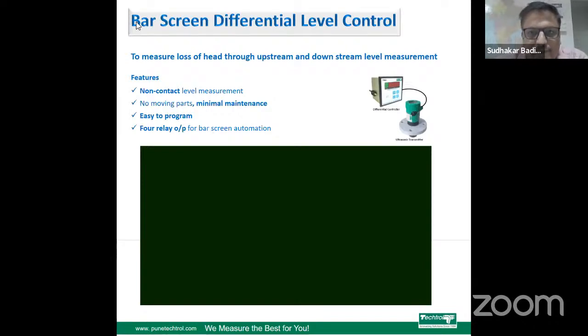So there are always upstream and downstream channels. In the upstream, one ultrasonic level transmitter is installed, and in the downstream also one ultrasonic level transmitter is installed. And in between there is a bar screen, which is obstructing the garbage and the solid particles. But because of the continuous flow and the continuous stacking of garbage and solid particles, one side level starts to increase, that is the upstream level. So there is a level difference between downstream and upstream.